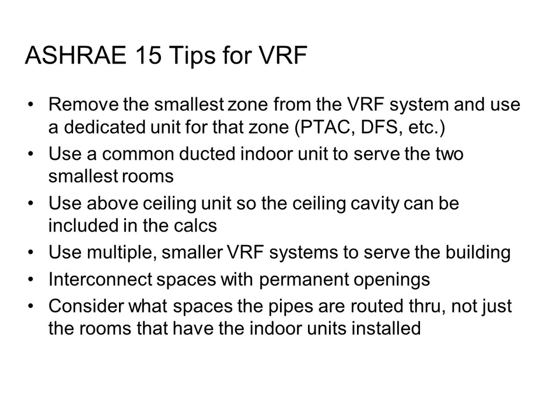Gustavo asks, how does it work when you run refrigerant pipe through chases, as far as being your smallest space and therefore dictating your volume? I would argue that a chase is a space that would not have occupants in it at any point in time, right? A corridor will have occupants in it. A vertical chase going up your building is not going to have occupants in it, and if there are any, it's going to be the mechanical contractor working on something, but not a normal, quote-unquote, unaware occupant. So I would argue that the chase is not something I have to consider for smallest volume because there are no people in there to have a problem.